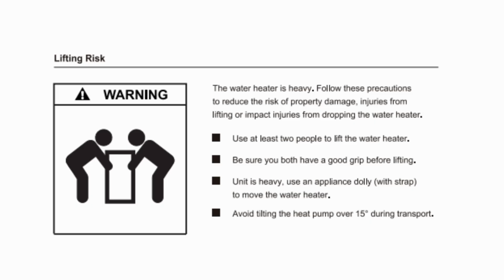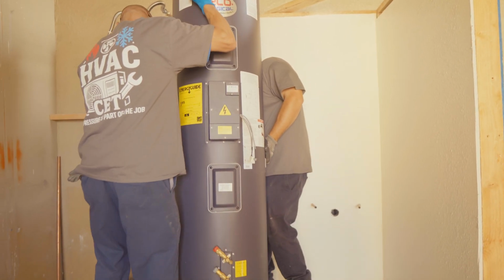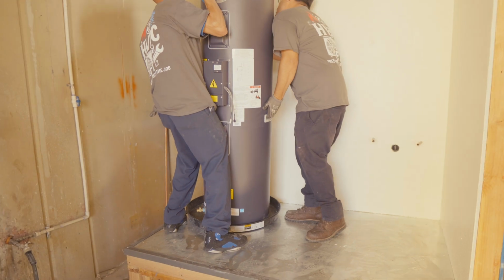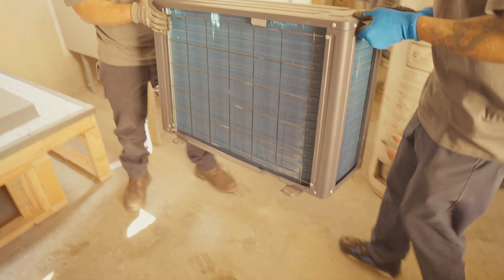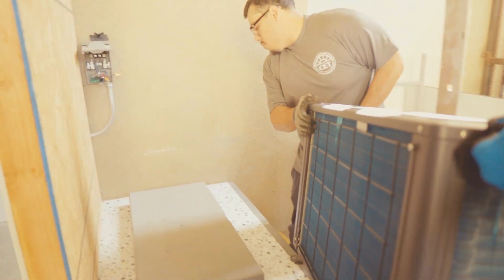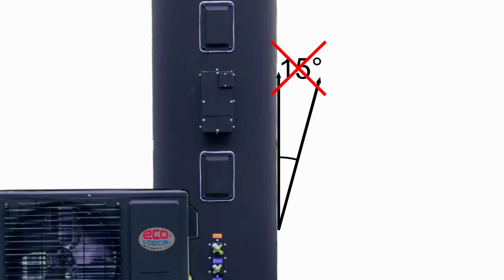Lifting risk. Heat pump water heaters are heavy and awkward to handle. Always use at least 2 people with a secure grip when lifting the unit. Use a dolly when moving it, and keep the heater upright. Do not tilt it more than 15 degrees to avoid damaging internal components.